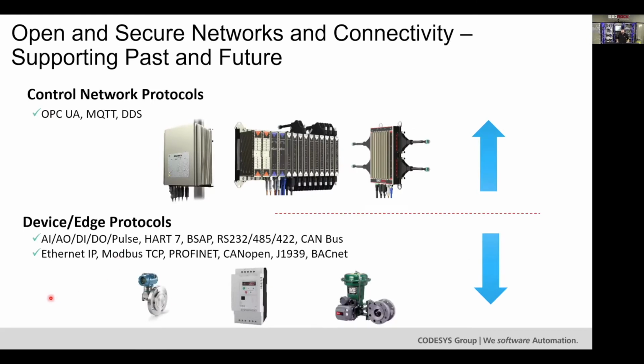Really, it allows you to secure your network activities, both past and future. So it supports all the latest protocols that you need to communicate with cutting edge technology for IIoT, as well as it rolls back to your legacy devices. So whether that's SCADA supervisory networks, OPC UA, MQTT, DDS, you have those networks, but you also support both the new and old, your standard DIDO, AIAO type physical inputs, as well as legacy protocols such as BSAP. You have CAN bus, Ethernet IP, Modbus, Profinet, CAN, J1939. The list kind of goes on for protocols that can be supported on the CODESYS environment.